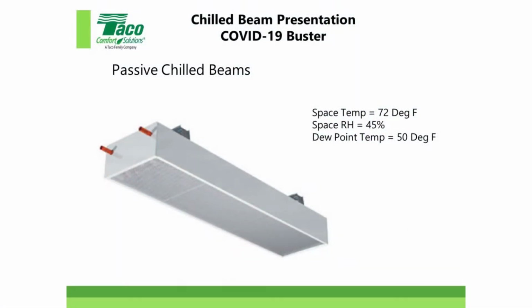Passive chill beams. These are only for cooling. And you can see the piping at the far end, so that would be a supply of chilled water and a return coming out. And then there's your space temperature and relative humidity. But again, the chilled water that goes in there has to be above the dew point. We're going to talk about some controls, and some possible controls, for a system like this as we go further. And again, this is only for chilled water. A lot of times you can see it's a simple sketch here. You can see it's hanging below the ceiling, right? And you might have some perforations, similar to the grates up here.